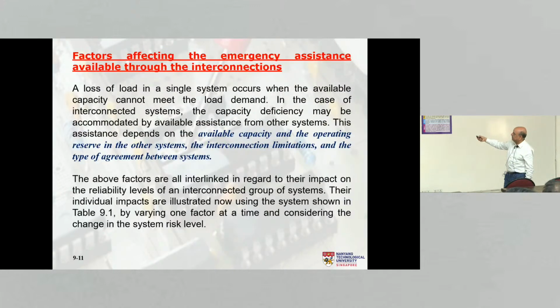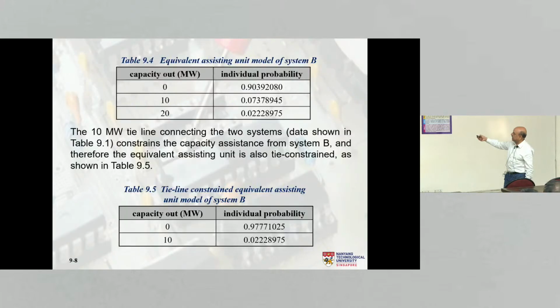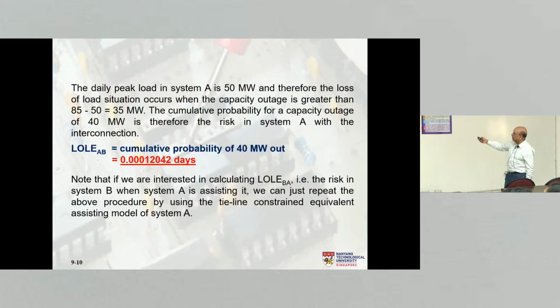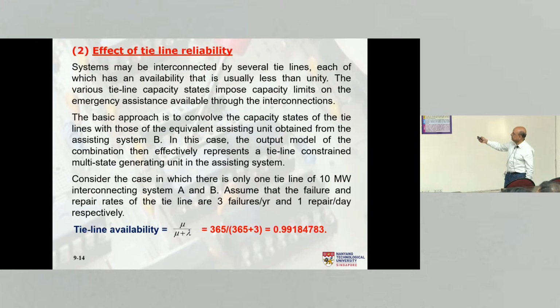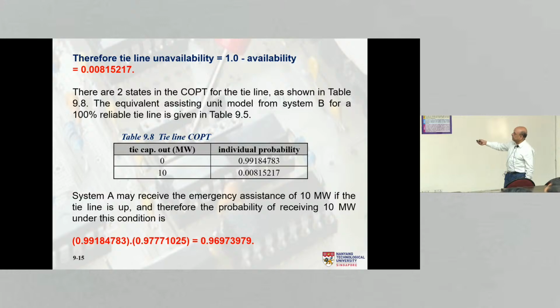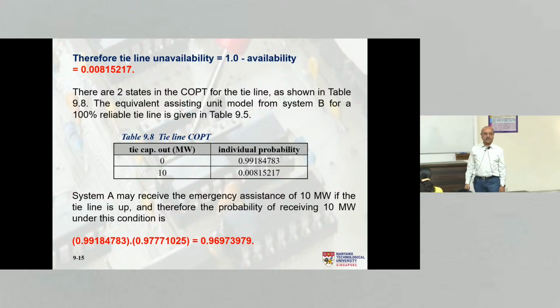If we go back here, a 100% reliable tie line is this one, correct? No outages in the tie line. But now we have a tie line which may not be available. So how do we modify it? So now the new table is this: tie line capacity, nothing is out. The individual tie line megawatt. These numbers. How did we find these numbers?